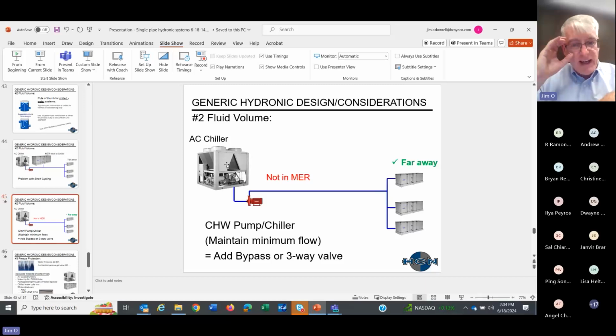So each of the chiller manufacturers has a maximum GPM, which you never get to, but they also have a minimum flow. Say that minimum chiller flow is at 50%. Out in your system, you have two-way valves, so your load is reducing. What could happen is that the water flow through your system is less than that minimum for the chiller. So you have to keep the water above that minimum through the chiller, and what they recommend is to add some type of bypass.